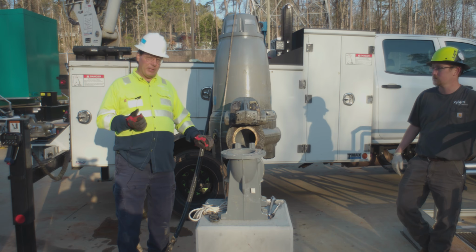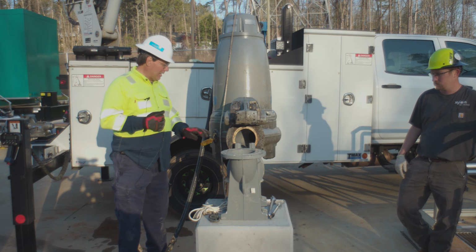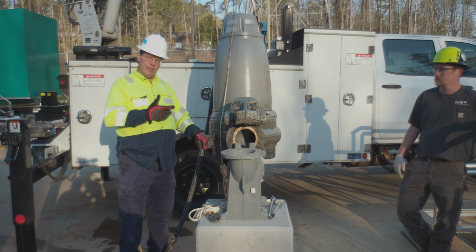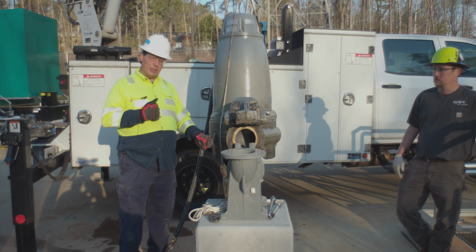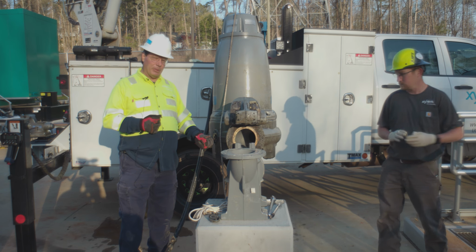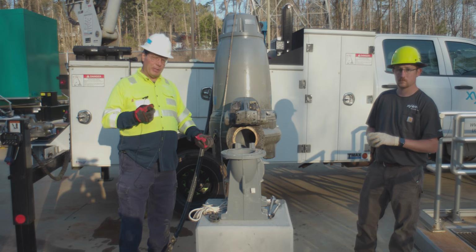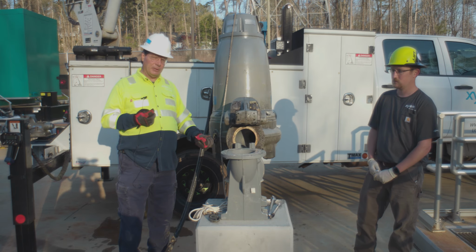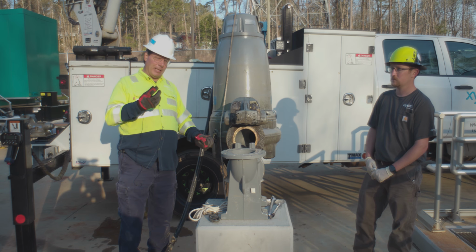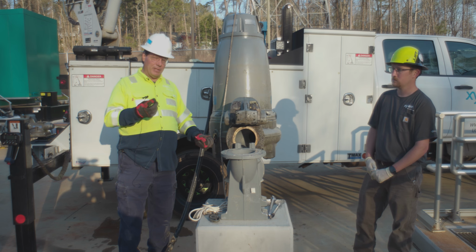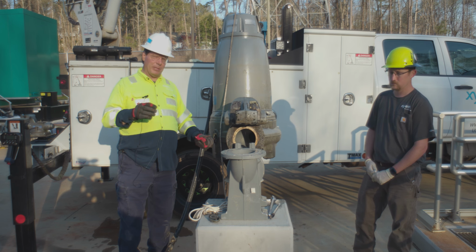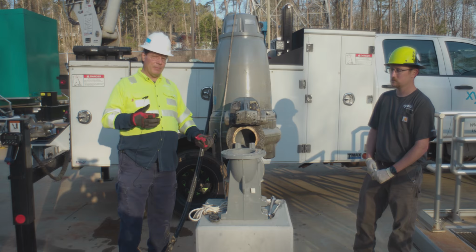We took the 14 millimeter wrench, and while I was holding the impeller, Garrett loosened it using a 14 millimeter wrench and removed the impeller bolt. Now that the impeller bolt's removed, we can take a 17 millimeter wrench and adjust the impeller collet and move the impeller up and down to get our 0.5 millimeter clearance off the bottom plate, the insert ring, the one that we showed you in the previous video.